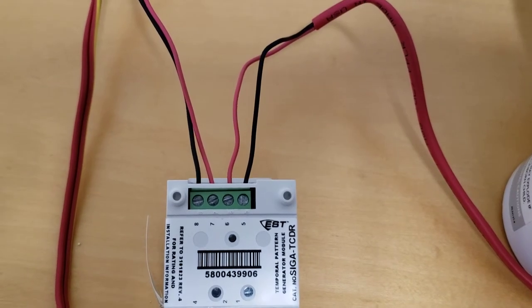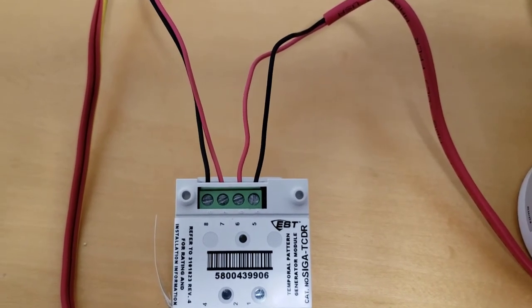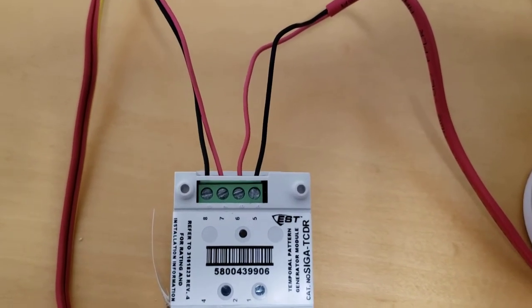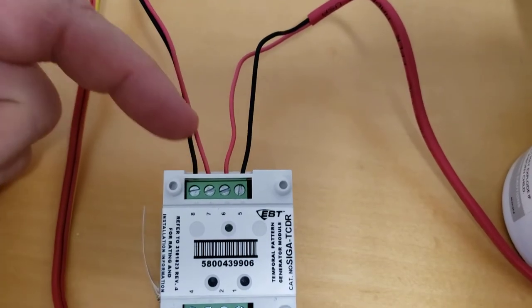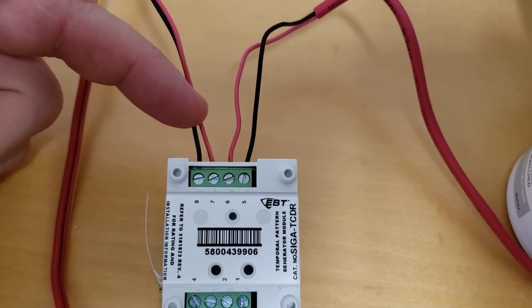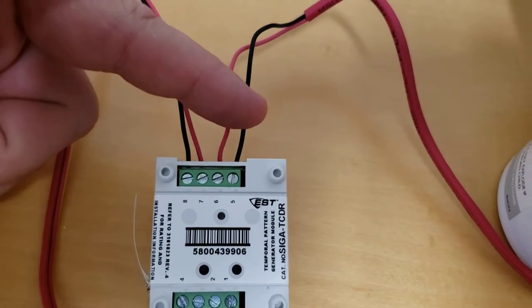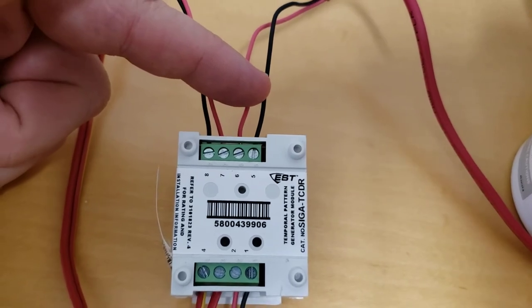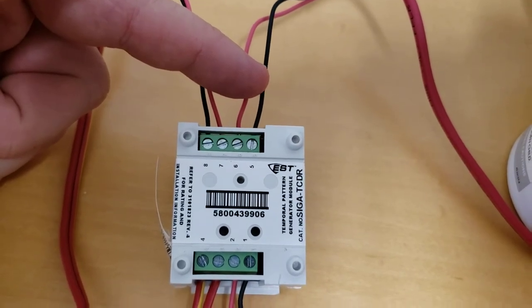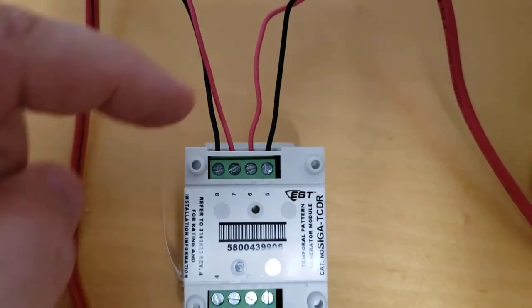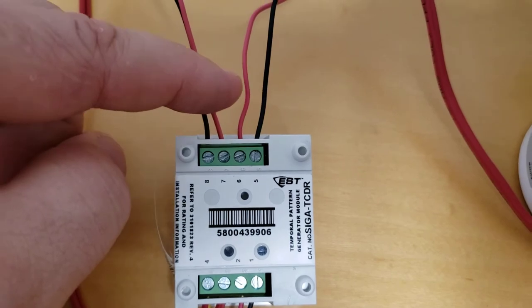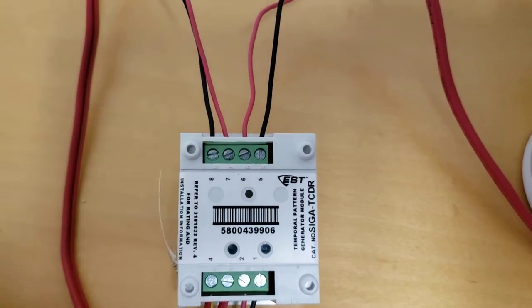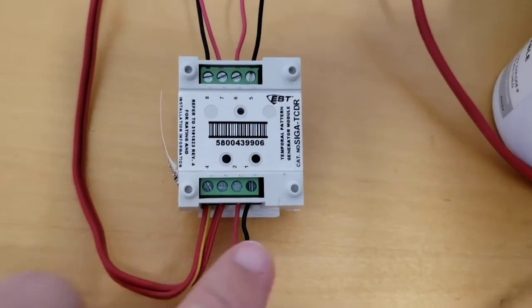Please note the correct wiring of a SIGA TCDR. This is the power source coming in from a constant 24 volts and this is going out to the SIGA AB4 GT base. It is negative, positive, positive, negative. That is the correct way to do it.